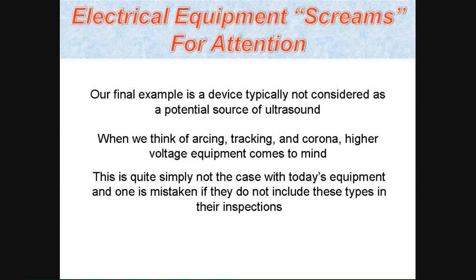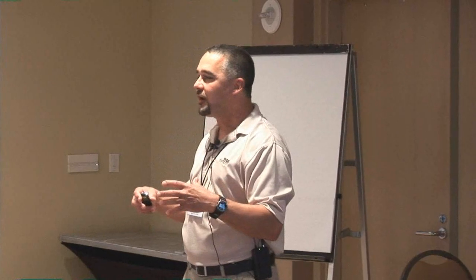The last example here comes from a place in Indiana that I was working, and typically you don't consider this a possible source of ultrasound. But what I always tell these guys is, when it's arcing, tracking, or corona, you think of higher voltages than I'm going to talk about here. That's simply not the case with today's equipment. Manufacturing standards, in my opinion, the quality of equipment we're using these days is not as good as it used to be in days gone by.